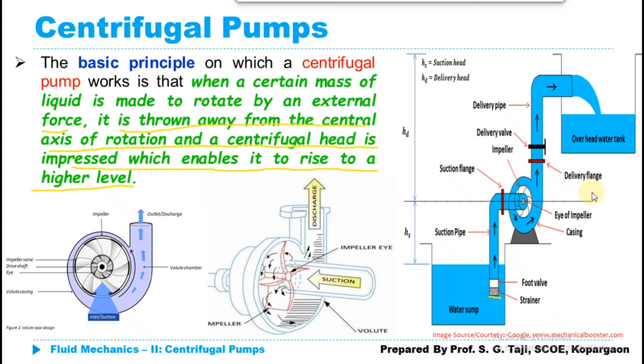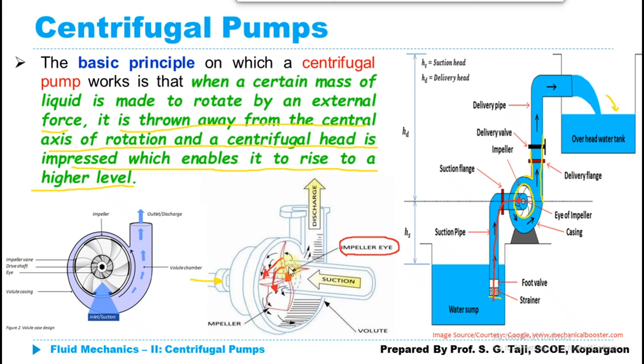In the arrangement of a centrifugal pump, the suction pipe is inserted into the sump and connected to the casing. Inside the casing, the impeller is coupled on the shaft. When the electric motor transmits mechanical energy through the shaft to the impeller, the impeller rotates, developing a suction head at its center — known as the eye of the impeller. Due to this suction head, water is drawn from the sump towards the eye of the impeller, and as the fluid contacts the rotating impeller, it also starts to rotate, generating centrifugal force.